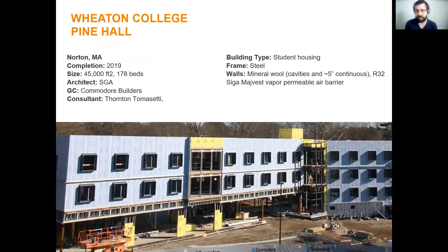The frames were dense packed with mineral wool, then they used sheathing on the outside - that yellow material you see. On top of the sheathing they used the blue SIGA material, the same product we saw at Finch, providing the air barrier around the entire building. Then on top of that they put a continuous layer of mineral wool, around 5 inches here. Part of that is because the steel frame provides a lot more thermal bridging than a wood frame, so they needed more continuous insulation to help offset the thermal bridging.